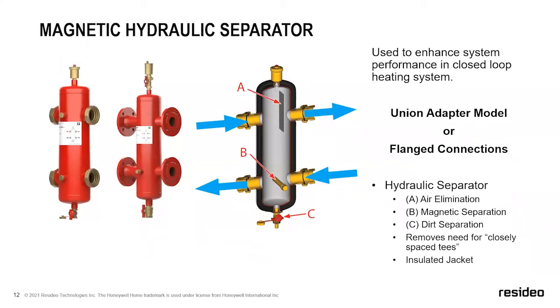That is becoming more and more important in modern hydronic systems because there's a big migration over to variable speed pumps. I started hearing rumors 10 years ago that codes are going to be changing, which are going to start requiring ECM motors. I haven't actually seen that take place, but that rumor's been around for about the last 10 years, to be honest. But there is a migration over to pumps with ECM motors, variable speed technology. And while it's a great product, it does come with some complications. One of the complications is those ECM motors are permanently magnetized, which means any kind of ferrous metals that are in the system go to the pump, stick in there, and basically they chew them up.